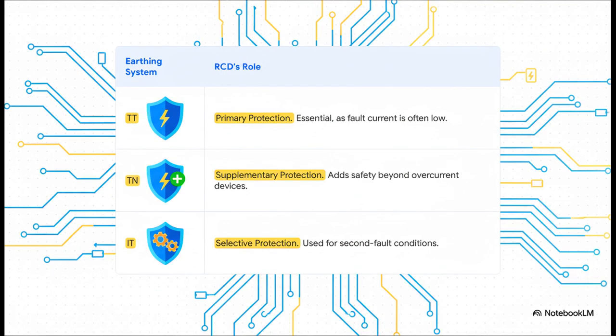So why does all that matter? Well, because the type of earthing system completely changes what the RCD's job is. In a TT system, the path to Earth has a lot of resistance, so the fault current is often too weak to trip a normal circuit breaker. In this case, the RCD is the primary protection. It's not optional, it's essential. In a TN system, the fault currents are huge and will trip a breaker, so the RCD acts as a vital supplementary protection, an extra layer of safety. And in an IT system, the RCD is used selectively, only to clear a fault after a second fault happens, to keep everything running.